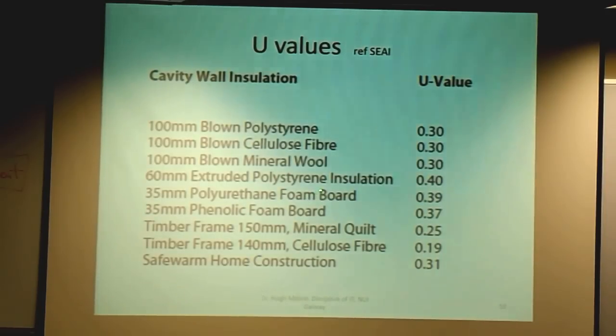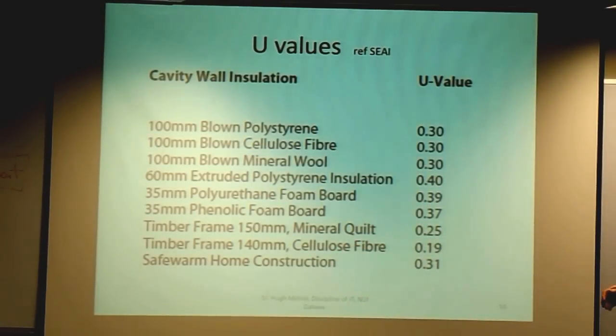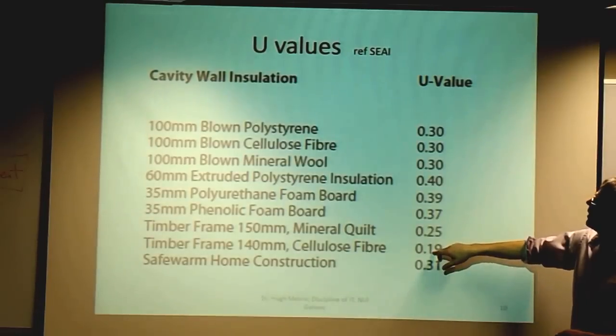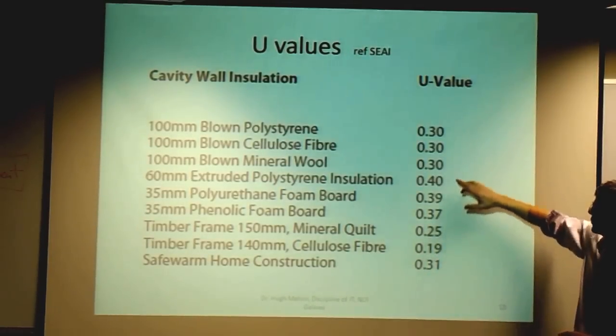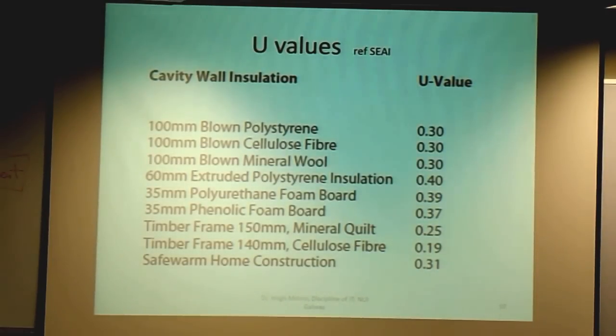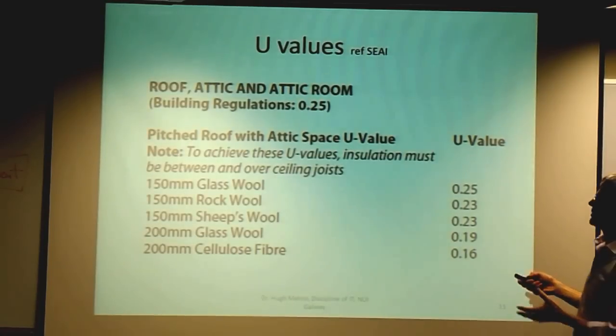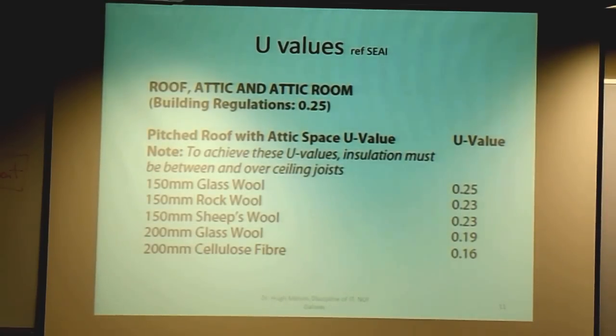As you go from here, we have a timber frame with cellulose fiber, which obviously has very high thermal resistance — the loss of energy is the lowest of them all. If you look at roofs, 200 millimeters of insulation at a U-value of 0.16. So that's how many joules of energy per second per meter squared, per degree Kelvin difference.